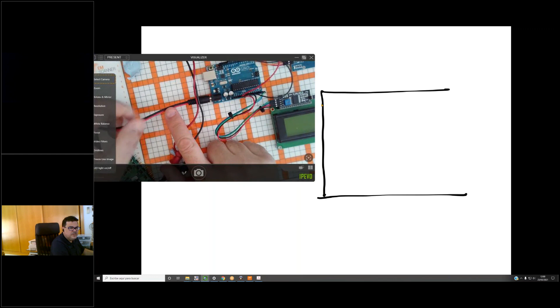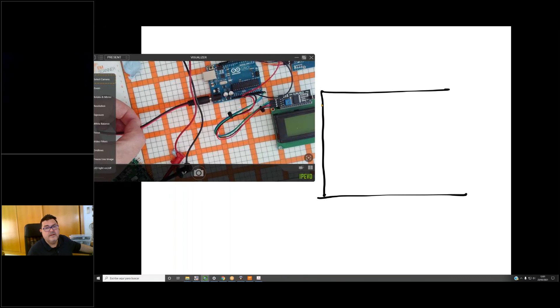Obviously, with the scanner, I am measuring both differential and common mode. But look at this, in the analysis on my camera. Let's go to this camera here. You can see that this cable has two wires, one close to the other. So with the scanner, I am measuring differential mode and common mode. But the problem that this cable is creating is basically common mode, because the magnetic field radiating from this cable to the environment is minimal. The differential mode current in the red wire is cancelled by the differential mode current in the other wire. It's different in this situation.